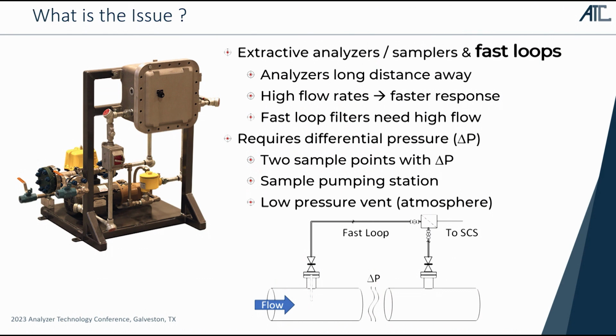The issue we're going to try to address with this is the fact that most extractive analyzers, most grab sampling stations, we'd like to have a fast loop there if we could. When we're looking at analytical measurements, we'd often like to get the sample there as quickly as possible, and especially if the analyzer or the grab sampling panel is a distance away from where we're going to do the measurement, we'd like to get high velocity flow rates over there.